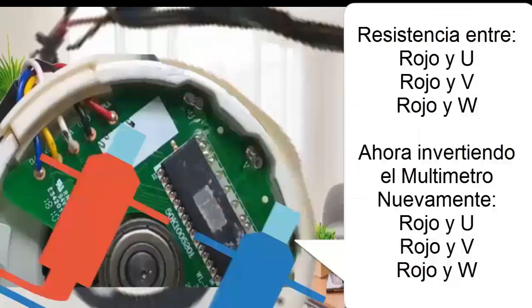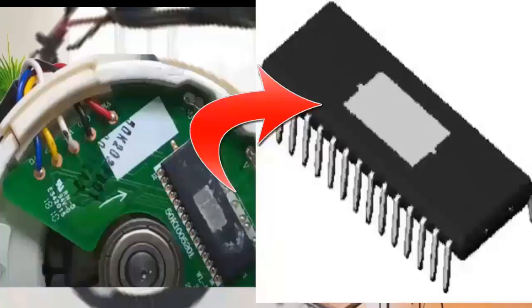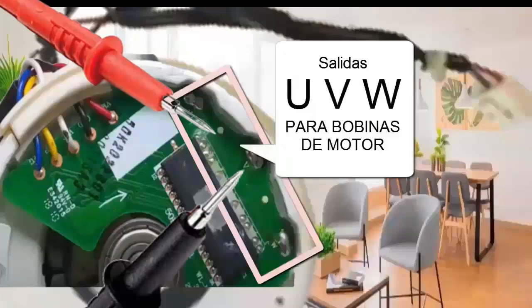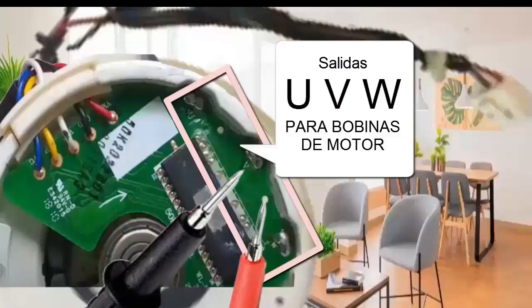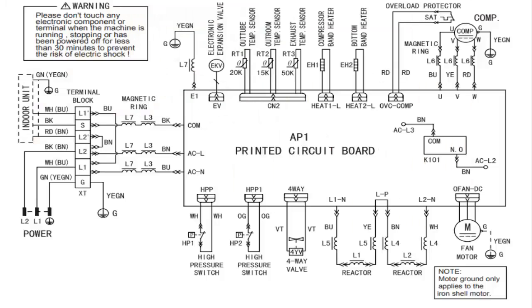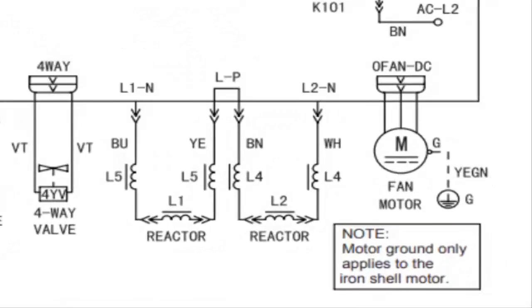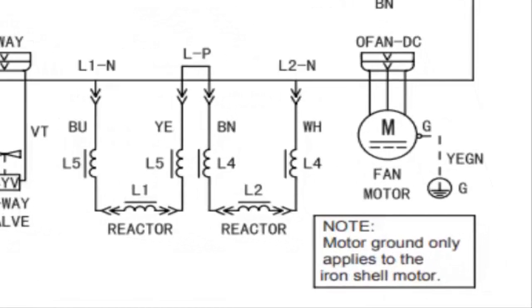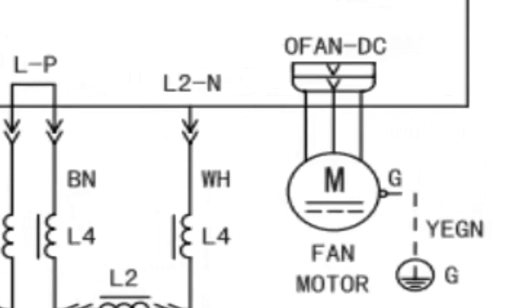7. When problems are detected in the internal electronic board of the BLDC motor, focus on the IPM controller on the board, which can be replaced with one of the same reference. If no electronic issues are observed, then disconnect the electronic board from the coils and measure the electrical resistance of these three. 8. When, according to the error code, the problem is located in the motor of the outdoor unit, the fan's electronic control is not inside the motor casing, but on the same external electronic board, which is why the fan is powered through only 3 wires.